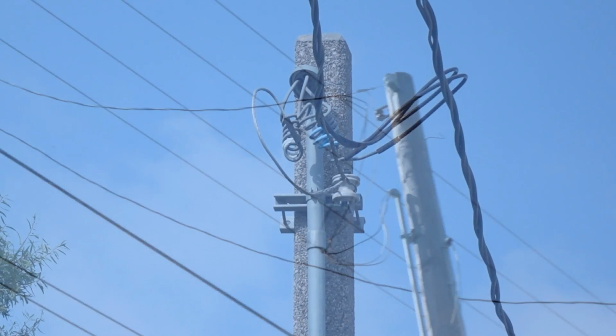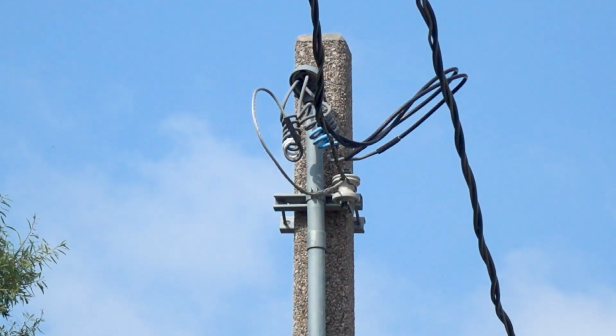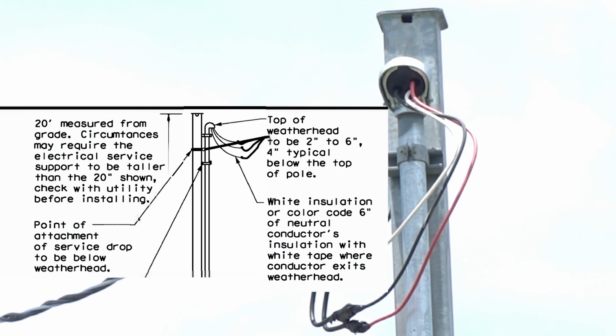The three conductors that come out of the conduit fitting at the top of the riser, or weatherhead, are called service entrance conductors. On TxDOT's electrical detail standard sheets, the height of the weatherhead is shown for each type of support structure TxDOT uses. For an overhead utility supply, the top of the weatherhead is between 2 to 6 inches from the top of the service support, with 4 inches being the typical distance. A visual estimate of this distance by the inspector from the ground will normally be adequate.